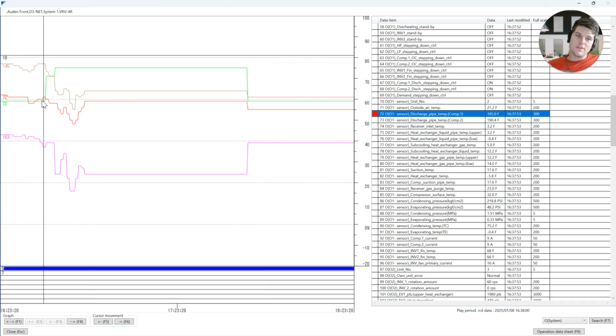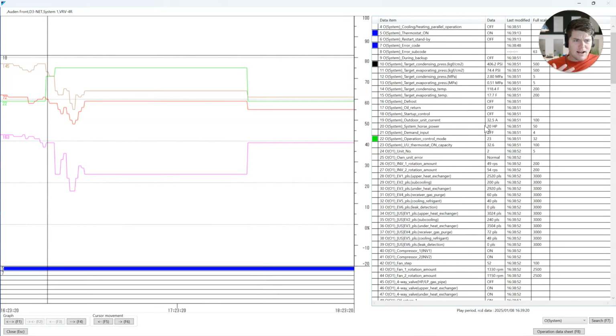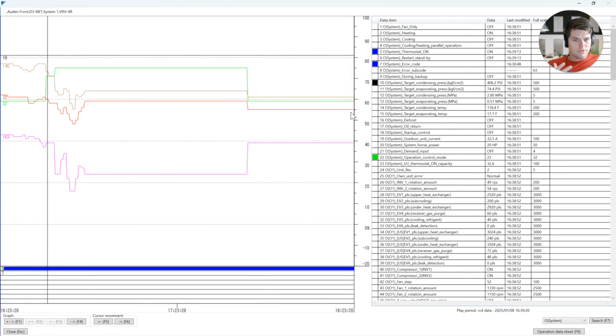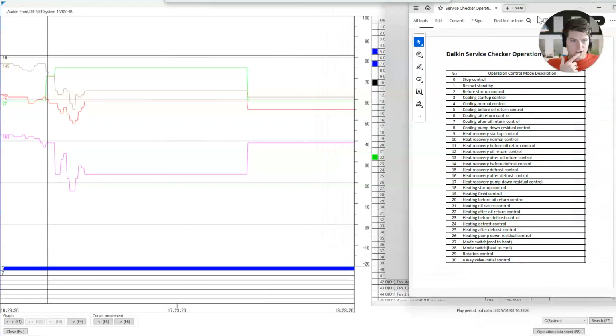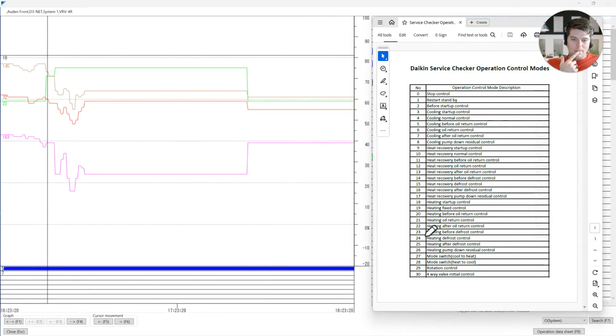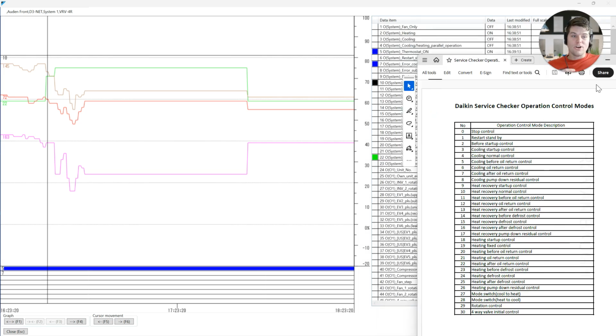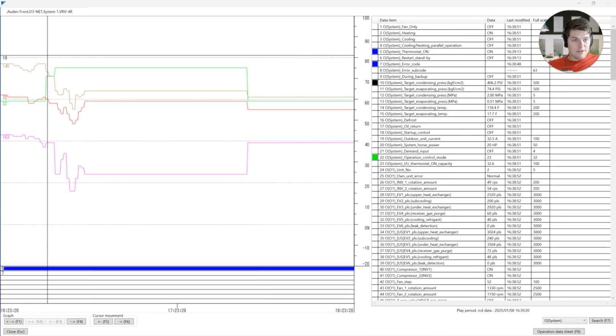It says I was in fixed heating control mode, but then I'm going to go into something else. And how do we figure that out? Mode 23. Okay, well, what is mode 23, I ask? Well, I'm going to go ahead and just cheat and jog this chart back over again. Wait a minute. Mode 23 is heating before defrost. It almost got me. Why does that matter? Now I know the system is doing what? It's no longer heating. It's getting ready for defrost.